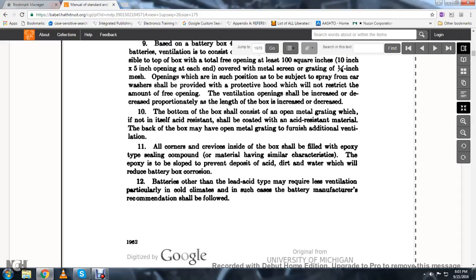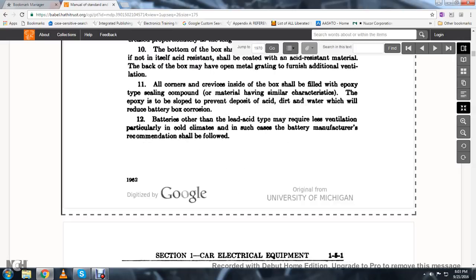The bottom of the box shall consist of an open metal grate which, if not itself acid resistant, should be coated with acid resistant material. The box back may have open metal grating to furnish added ventilation. All corners and crevices inside the box should be filled with epoxy type sealing compound or material with similar characteristics, sloped to prevent the deposit of acid, dirt, and water, and to reduce battery box corrosion.